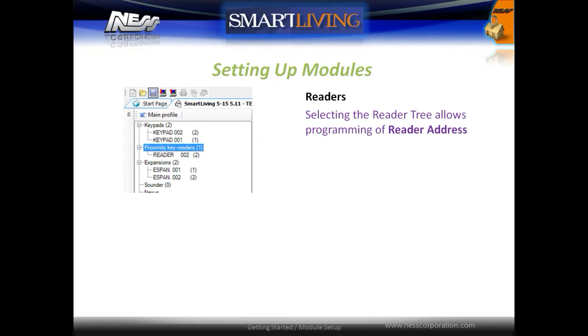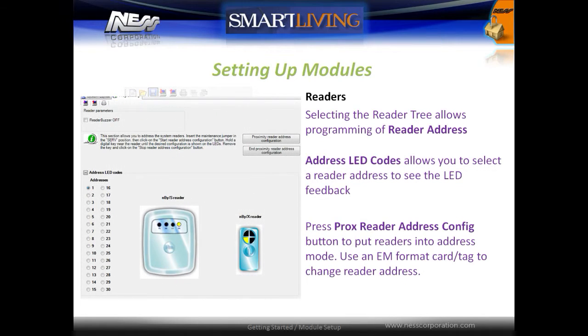Selecting the Proximity Key Readers tree allows programming of reader addresses. Opening the Address LED codes allows you to select a reader's address and see the LED feedback that will be required. Pressing the Proximity Reader Address Configuration button will put all card readers into address setting mode. Use an EM format card or tag to change reader addresses by badging the card against the reader to change the LED feedback. Click the End Proximity Reader Address button when done.